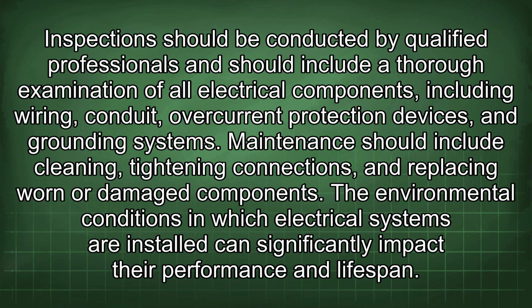Inspection should be conducted by qualified professionals and should include a thorough examination of all electrical components, including wiring, conduit, overcurrent protection devices, and grounding systems. Maintenance should include cleaning, tightening connections, and replacing worn or damaged components.